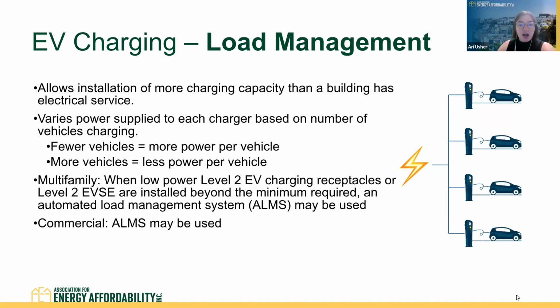Load management. An automated load management system, or ALMS, can be used to keep costs down for that electrical capacity. It allows the installation of more charging capacity than a building has electrical service for, by varying the power supply to each charger based on the number of vehicles charging. If fewer vehicles are charging, more power is distributed to each vehicle; if more vehicles are charging, each gets less power. This is actually allowed per code. CalGreen does allow an ALMS to be used when the total number of EV spaces installed is beyond the minimum requirement. For commercial buildings, ALMS can be used at any time.